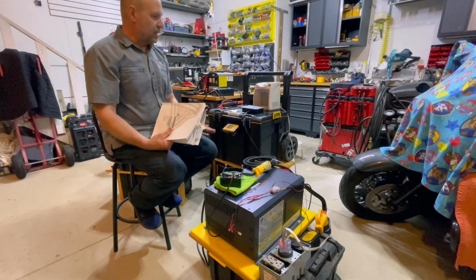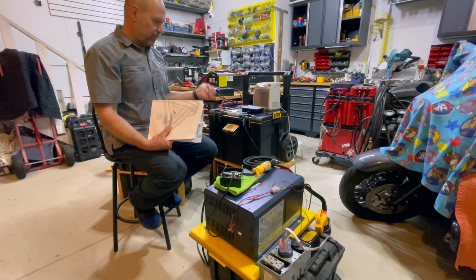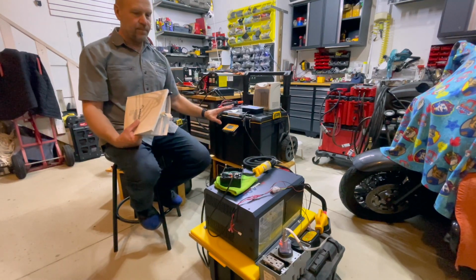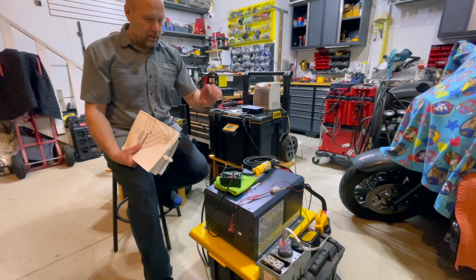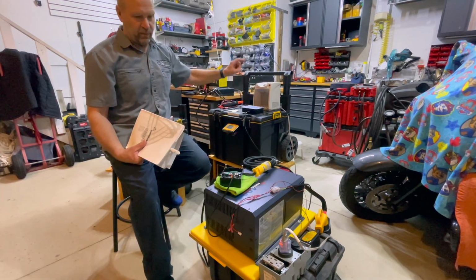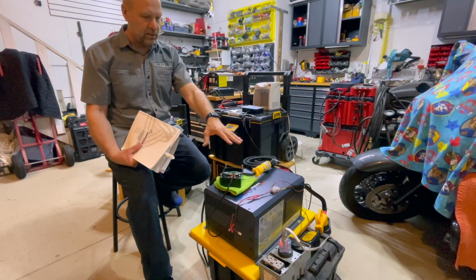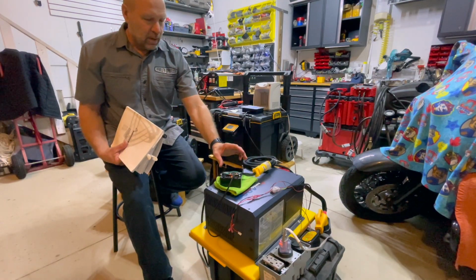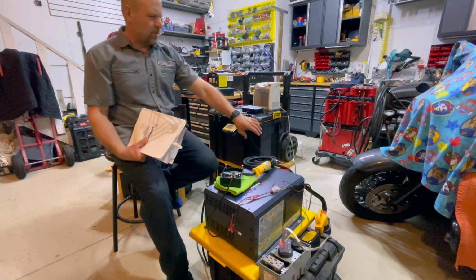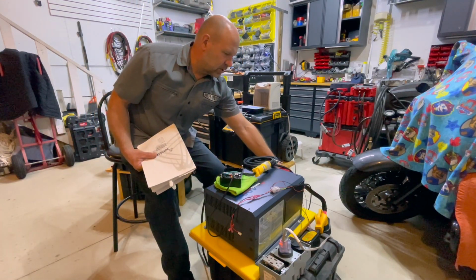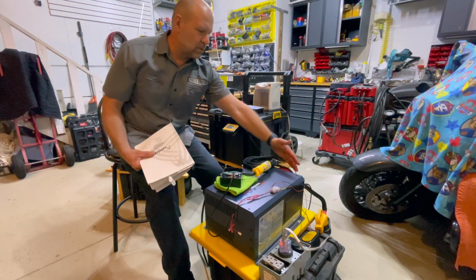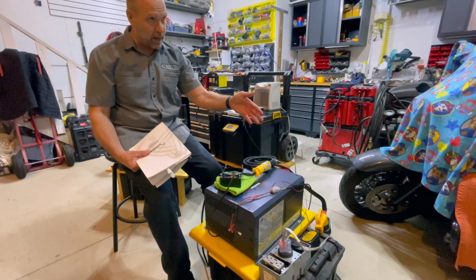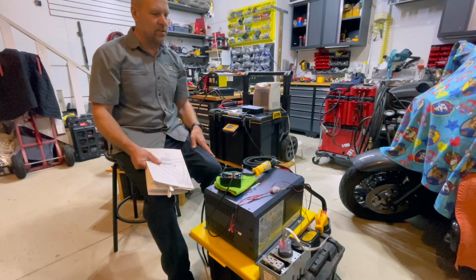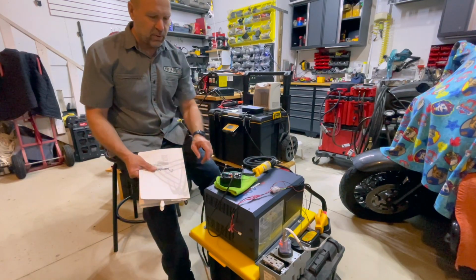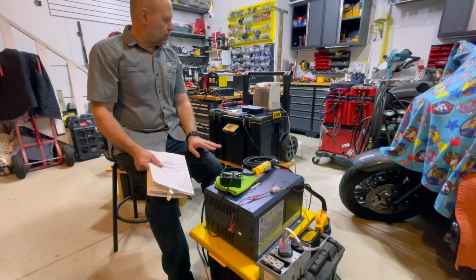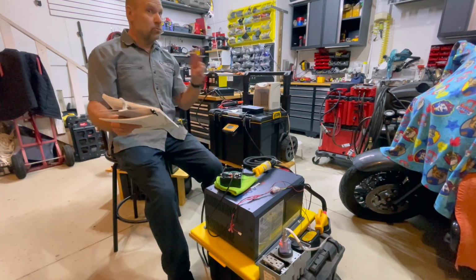This is set up kind of the same way as I have the other ones, where I have the inverter and controls from the batteries telling the inverter -- I think it's by an open circuit. No, this is also by a voltage. It's a low amperage, like milliamps, but it still has to see some type of voltage. This one also has to see a voltage as well. So they're both set up similarly, but on two different signals.